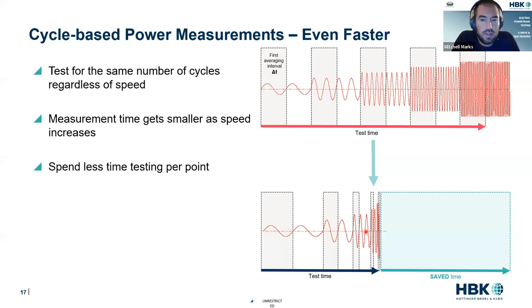And just by cleverly changing how we do our testing, because of that cycle detect, we can go from having a timed basis to having a cycle basis. And we can save a lot of time because as the machine goes faster, we can take less time to make a comparable measurement. So again, that cycle detect allows us to test very quickly, to get those efficiency maps very quickly. So I hope this sinks in. And again, we can take this offline in a different session, but the cycle detect allows us to measure very quickly and save you that time and money.